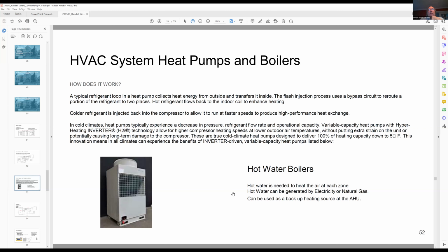A lot of our designs add backup heating elements, whether a gas-fired boiler or an electric boiler. We can discuss being completely electrified, or using natural gas as a backup to the system. Either way, when heat pumps get below 20 degrees, we'd like to switch from the heat pump to an electric or gas-fired boiler to provide heat, which also serves as a backup.